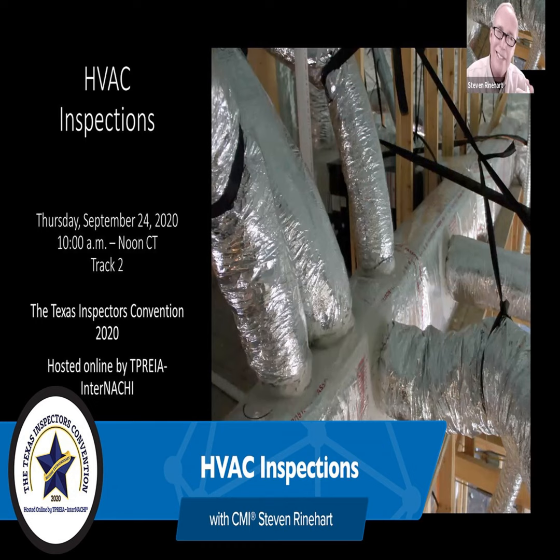So if you put a standard in there and you intend to put what you got, I would also say where I got that at, because it's going to vary unless you're poking holes in the plenums. If you got some temperature gauges and you put one in the return, and maybe you open up that updraft in the closet and you see there's a little bitty pencil-sized hole in that supply plenum where somebody else has done it, yeah, you could put it. So if you got temperatures on either side of that coil, you would be the most accurate, and you still would not have anything in the standard to reference to.